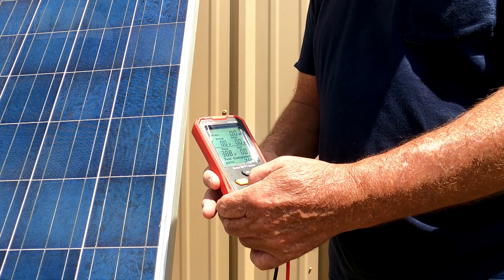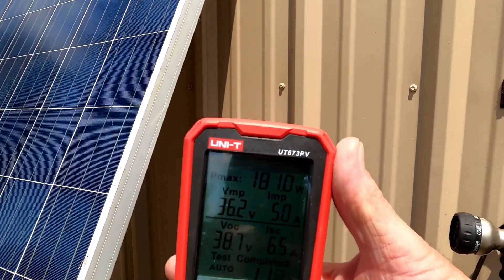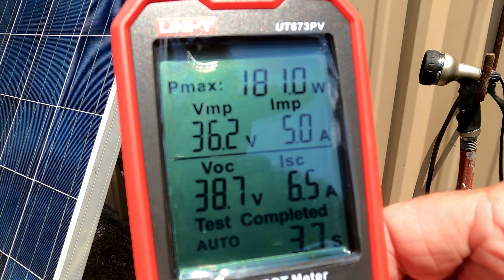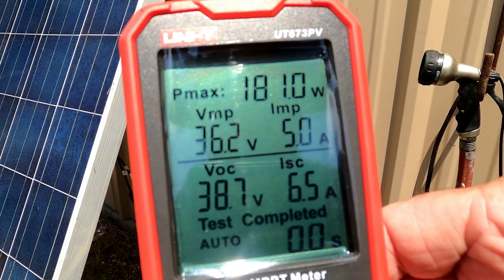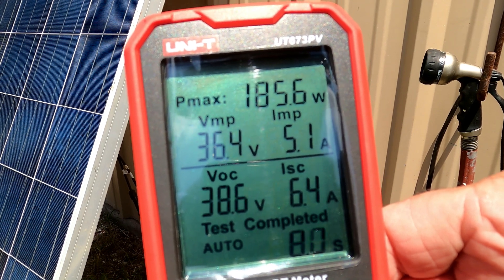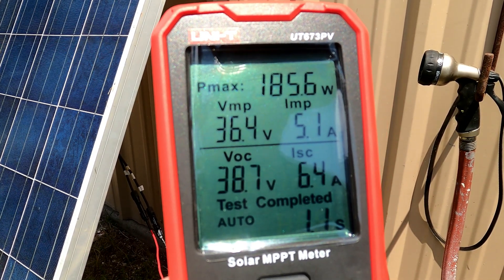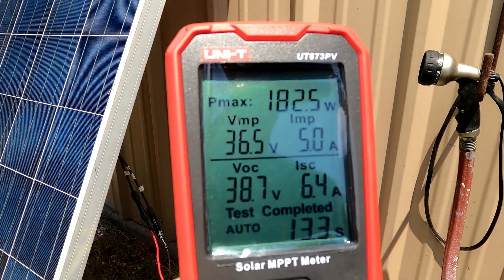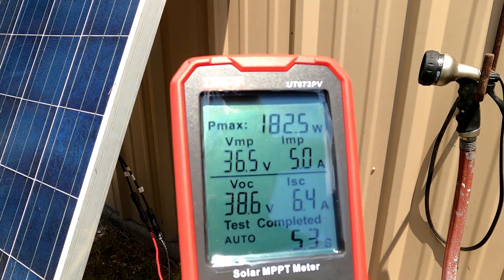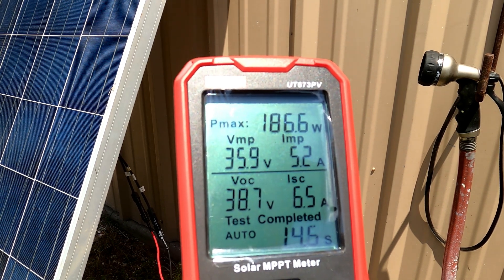We'll go automatic. Let me get the camera to see this a little bit better. Sorry about all the confusion, folks — there's a lot of glare and I'm trying to get this where you can read it. This thing is going to refresh about every 15 seconds. So you can see this solar panel here is putting out 185.6 watts, 5.1 amps, 36.4 volts. The VOC is 38.7, 6.4 amps. Test completed is automatic — this thing will just keep switching over and over as the sun changes, so will the watts coming out of the panel.